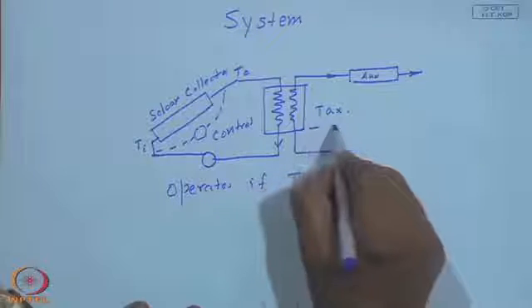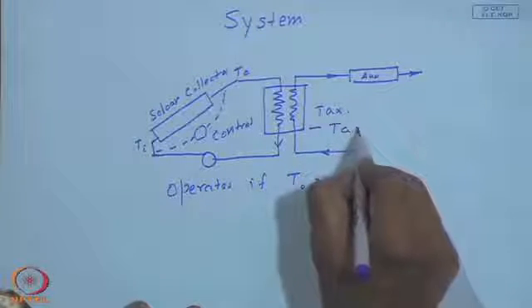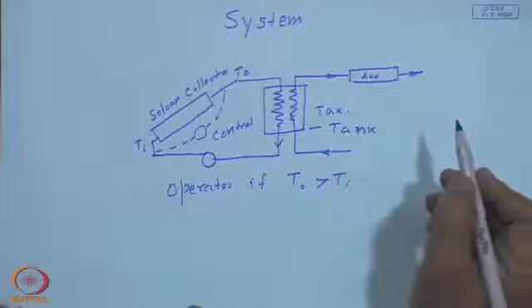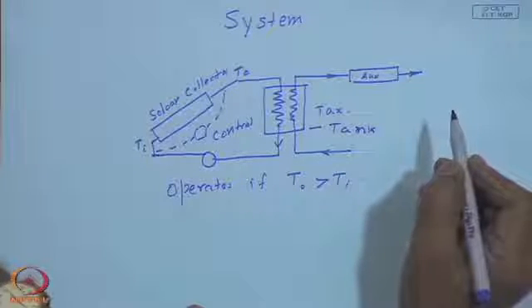Now this is an auxiliary tank. To give an example: somebody designs for a family of 4 that about 60 or 120 liters of hot water are required per day. So the solar collector sizing is found to be about 3 square meters roughly, and the pump and everything is put in place, but they forgot to put in a tank. Unless the requirement matches the solar radiation, taking little water in the morning when the sun is not so hot and more water around 12 o'clock, the utility of the system can only be felt then.